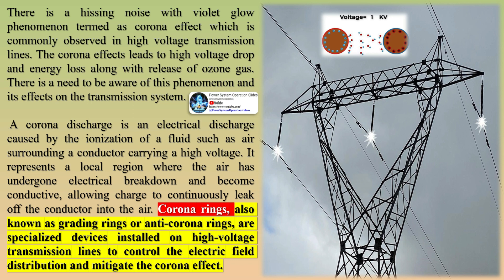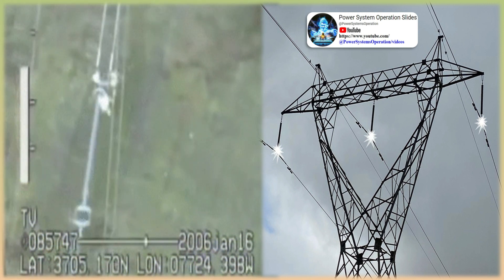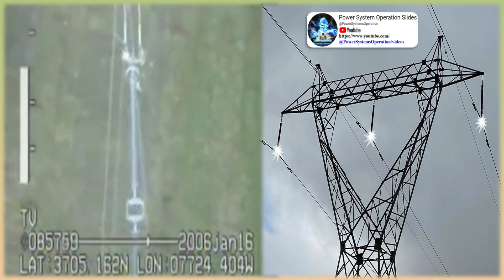The ionized air acts as a virtual conductor, producing a hissing sound with a luminous violet glow. This hissing noise with violet glow phenomenon, termed the corona effect, is commonly observed in high-voltage transmission lines. The corona effect leads to high voltage drop and energy loss, along with the release of ozone gas. There is a need to be aware of this phenomenon and its effects on the transmission system.